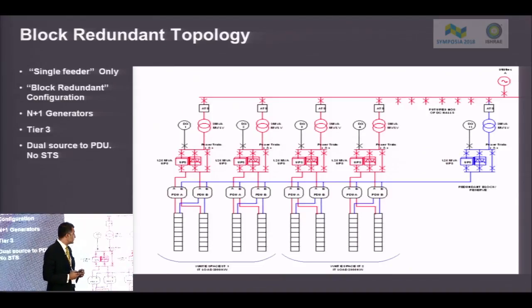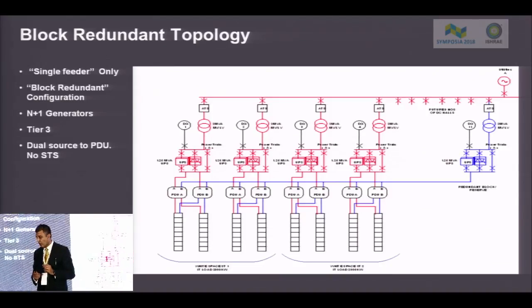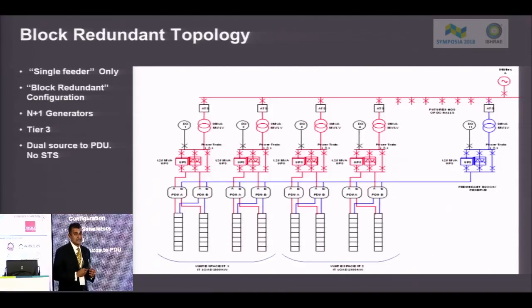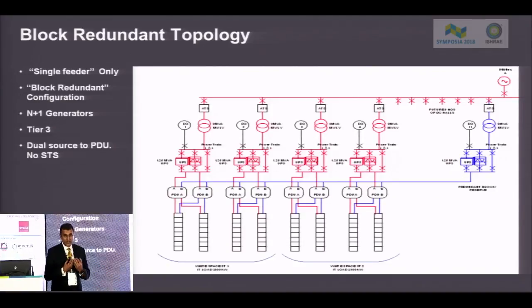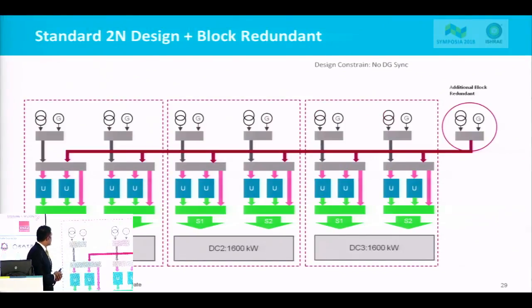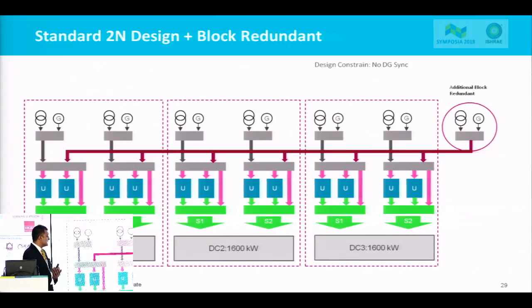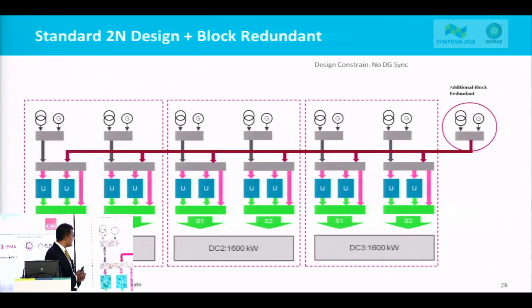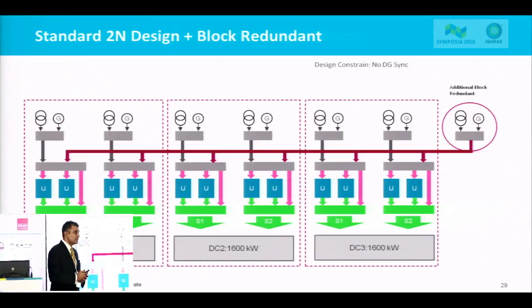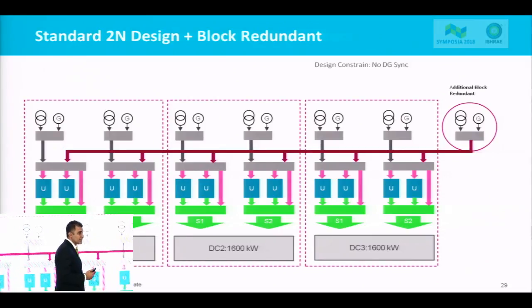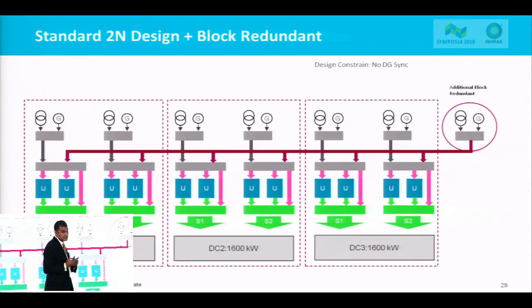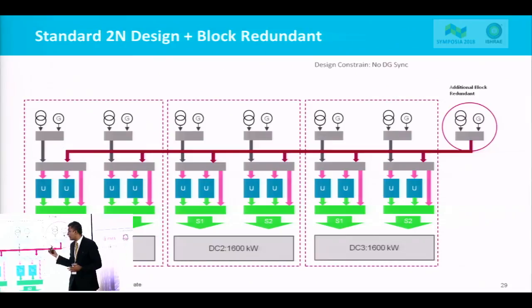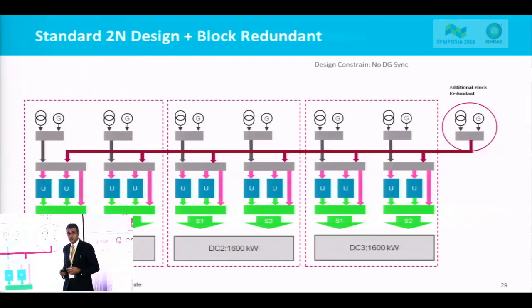But we also must note, this is not a solution for all geographies or all countries or all instances. It's a case by case, depending on the requirements. Also, in some cases, it will require highly skilled personnel to manage the site. Next is looking at a block redundant topology on the generators. We can also reduce the number of equipment, in this case the generators, and offer a block redundant topology to provide the 2N topology.